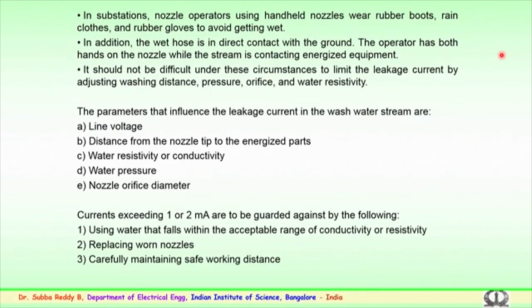So, the parameters that influence the leakage current in the washing water stream are the line voltage, that is important: what is the voltage at which the insulators are being cleaned, what is the voltage level the equipment is operated at; the distance from the nozzle tip to the energized part, which is a very important point; water resistivity or conductivity, which plays a role; the water pressure, that is the operation of the water jet at a certain pressure, which is also an important parameter that could influence the leakage current; and the nozzle or orifice diameter. So, the nozzle diameter which is being used also plays an important part in influencing the leakage current.